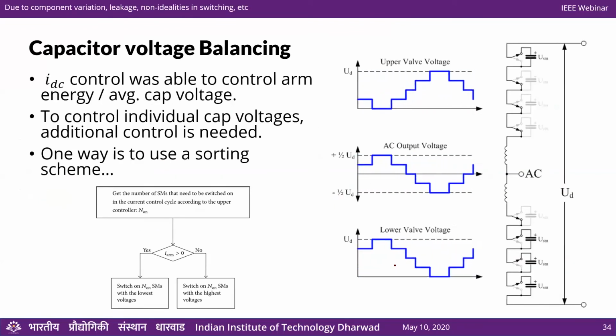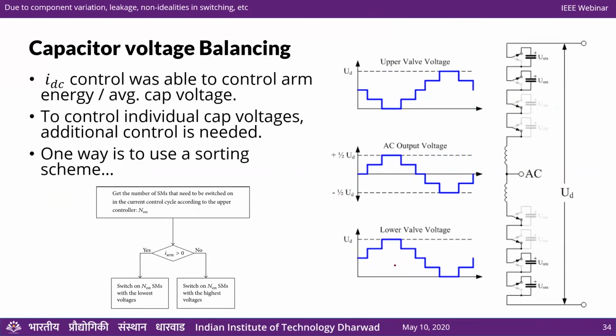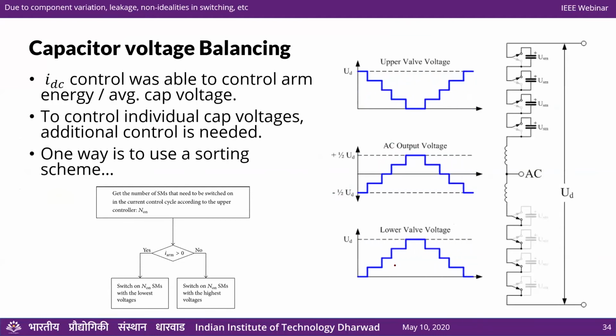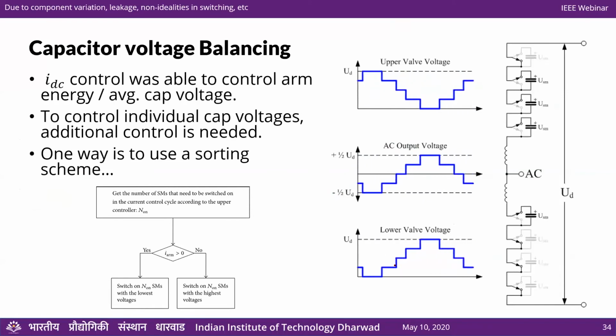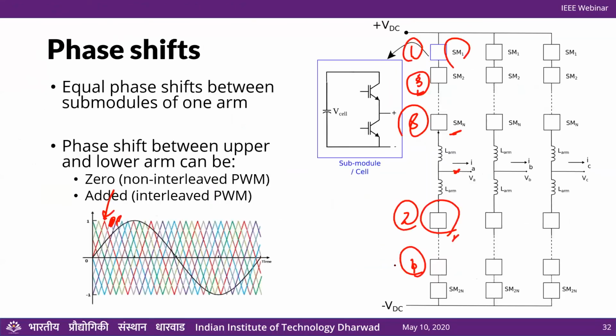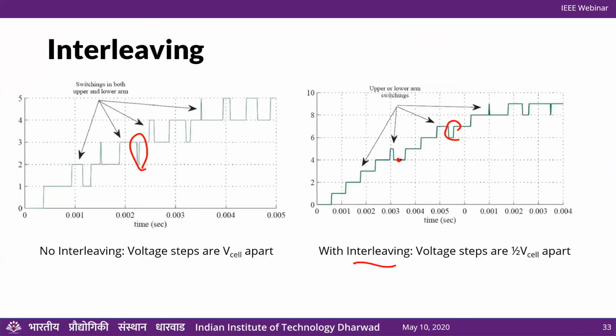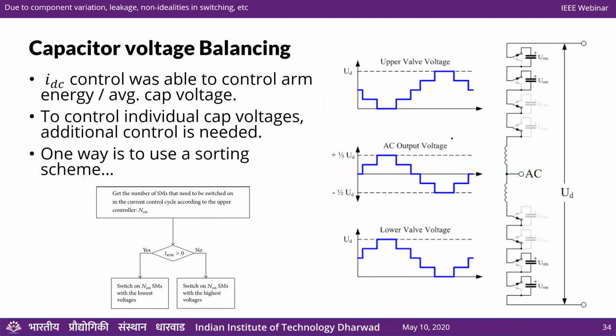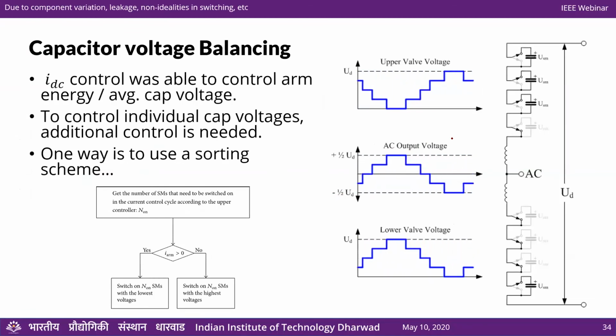Now getting back to which module to turn on. Our modulation scheme tells us to turn on a module, turn off a module, increase voltage, or decrease voltage. Let's say at this point the modulation scheme says we need to switch on one module, and at this point we want to switch off one module. But which module should be turned off? That is determined by our capacitor voltage balancing criteria.